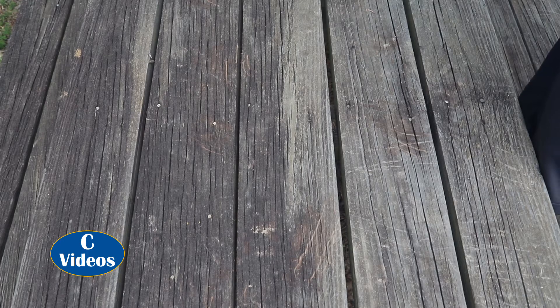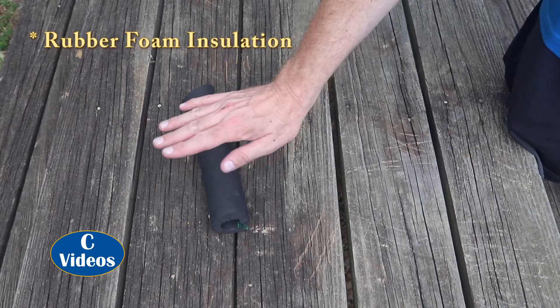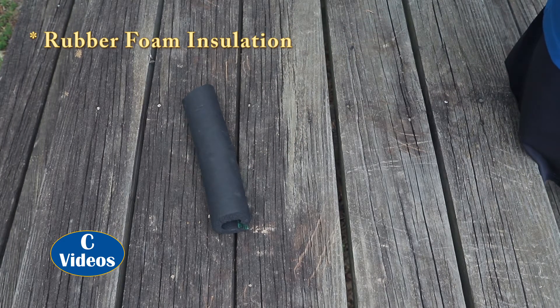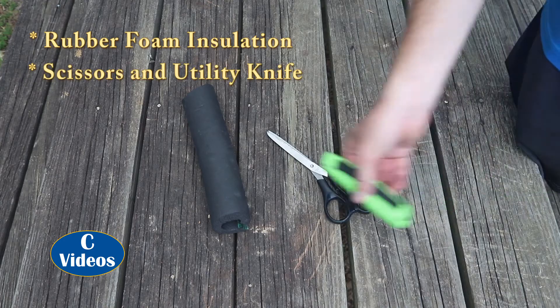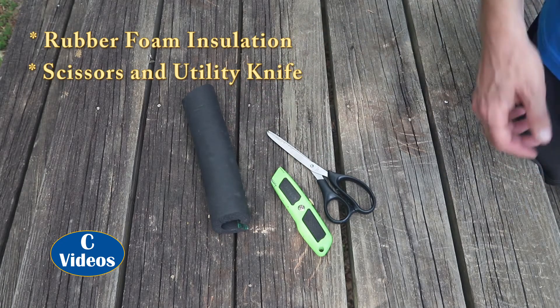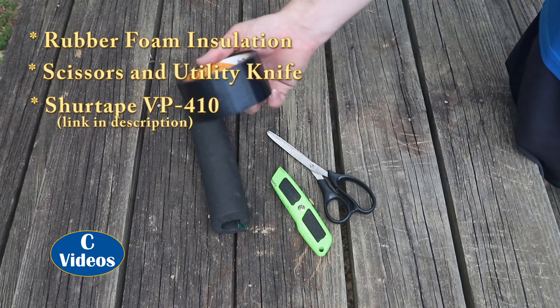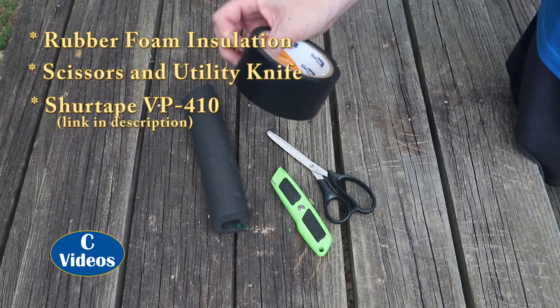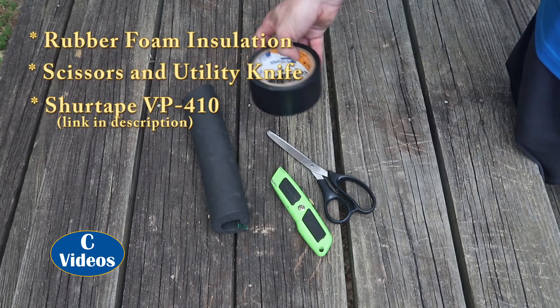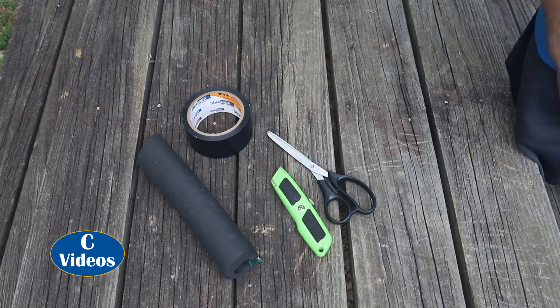Let's take a look at the supplies we'll need today. Of course we'll need rubber foam insulation. You can also go with poly foam, but my AC tech friend highly recommends the rubber foam for outside line sets. We'll need some scissors and a utility knife for cutting off the old insulation and for cutting the new insulation to size. And of course we'll need some tape — I like to use the Shurtape VP-410. This is vinyl tape, kind of like electrical tape but waterproof. It's meant for line sets and it's made by Shurtape. That's all the supplies we'll need.